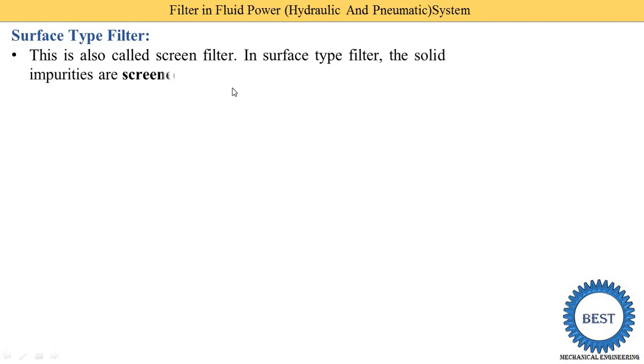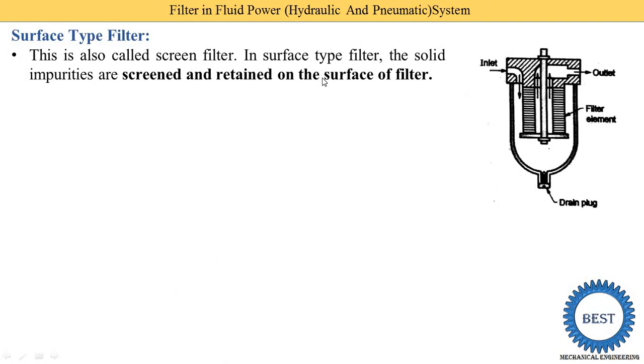The first one is the surface type filter, also called screen filter. In a surface type filter, solid impurities are screened and retained on the surface of the filter. Every filter has some basic components: the inlet, filter element, outlet, and drain plug. The drain plug is generally used to empty the filter. According to where the dust is collected, the filter is classified as surface, depth, or edge type.